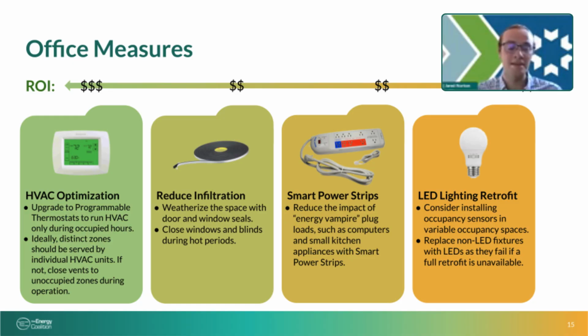You can set 7-day schedules with your standard occupancy. You can program heating and cooling set points both during standard occupancy hours and also during unoccupied hours, setting those set points back when no one's in the space so that you're not running HVAC when you don't have to.